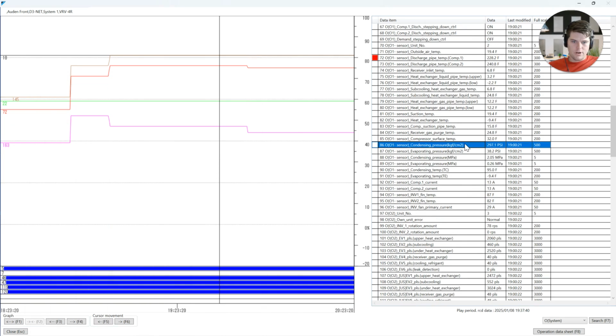Condensing pressure, not condensing pressure, sorry. Condensing saturation temperature, right? We don't talk in pressure anymore. That's below us as VRF techs, right? We don't talk about pressure, we talk about saturation temperature. Come on now, guys. 95 degrees, right?